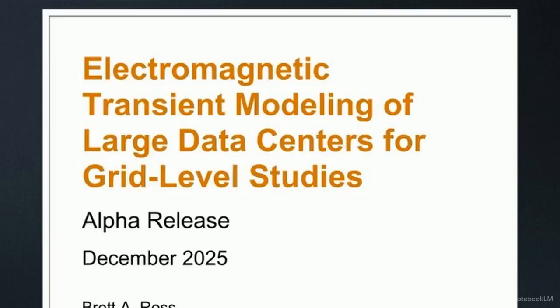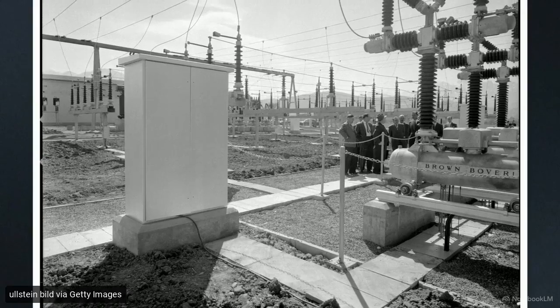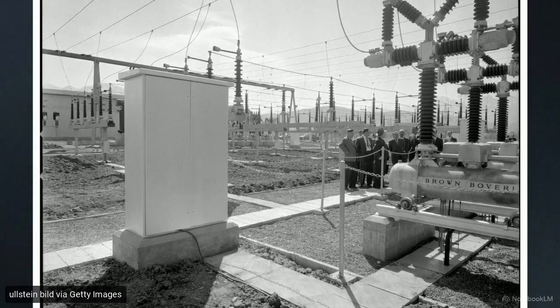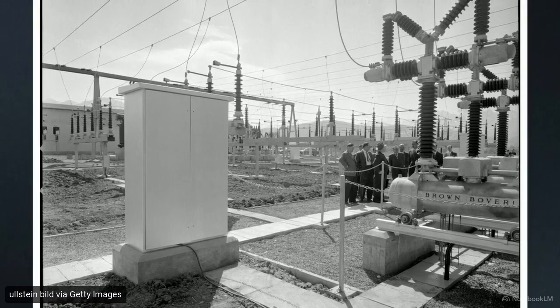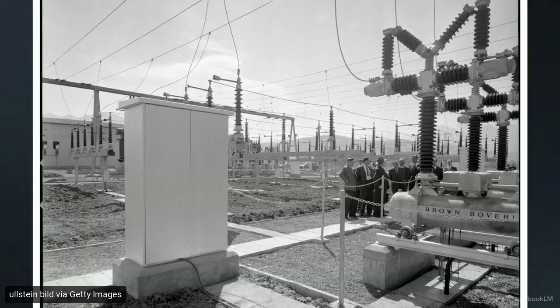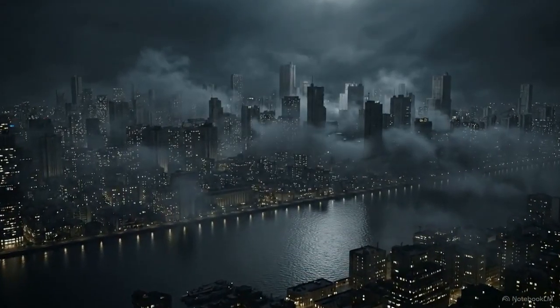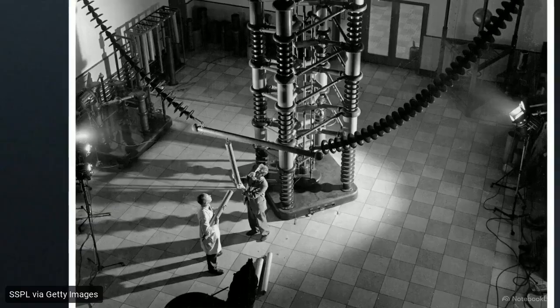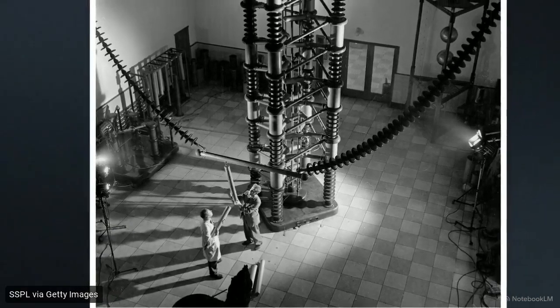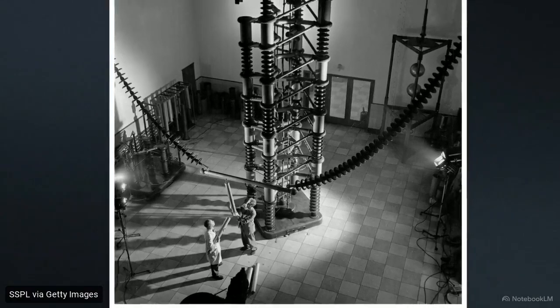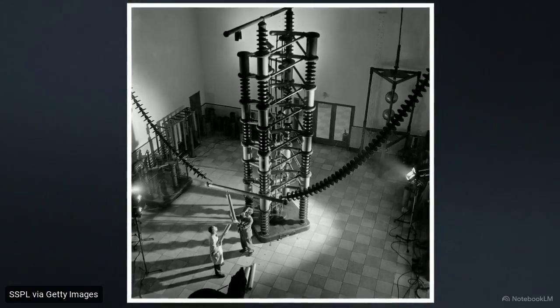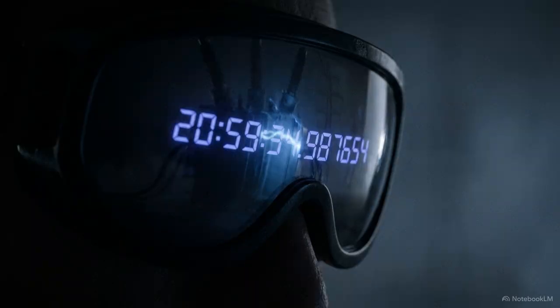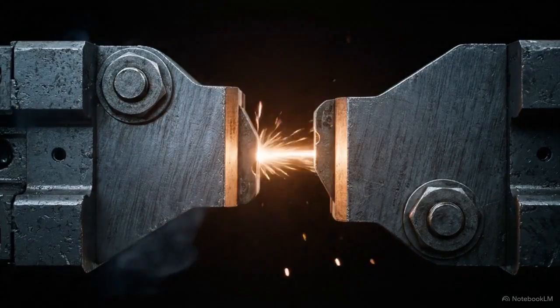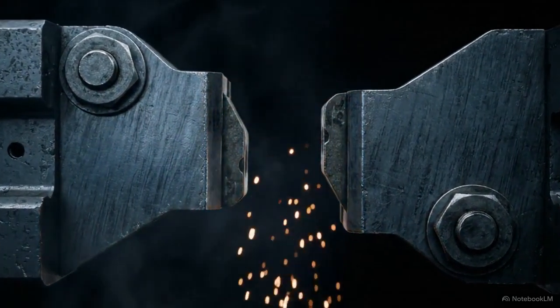To know exactly what mitigation is needed, planners rely on electromagnetic transient, or EMT, simulations. These models predict these hidden TRV stresses, allowing utilities to specify the exact equipment required long before any construction begins. We so often take it completely for granted when a fault is cleared and the city lights stay on. But every successful circuit interruption is an invisible orchestration of advanced physics, precise hardware timing, and rigorous forward planning. An engineer's control over the grid is measured by their mastery of the microsecond, the incredible ability to predict and win the violent race that only begins once the power is cut.